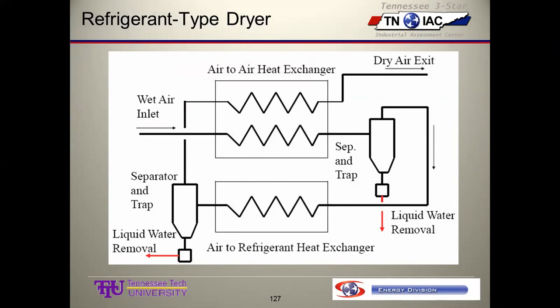Just to review, the desiccant will get you a nominal dew point of the compressed air in the pipe of minus 40 Fahrenheit. Now, I've seen at Honda in Marysville, Ohio, they're painting lots of cars, and they actually use both a refrigerated air dryer as the first stage and a desiccant dryer as a second stage, and they were achieving dew points of minus probably 75 to minus 100 Fahrenheit. It was overkill, but when you're painting cars, you don't want to take a chance of screwing up. But anyway, the desiccant technology basically can strip a tremendous amount of moisture out of the air. It's expensive to purchase, and it's expensive to operate, as we'll see in later slides.